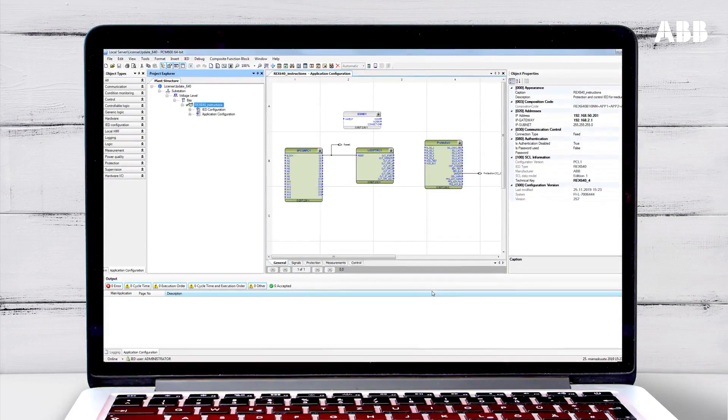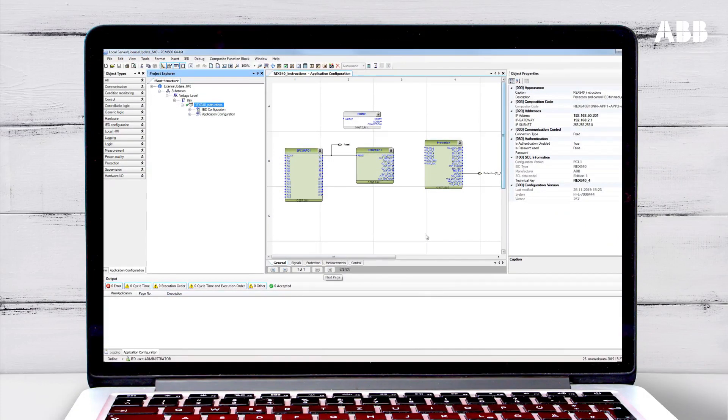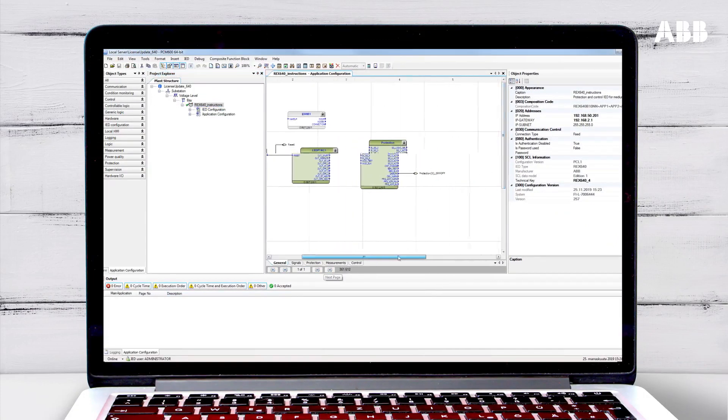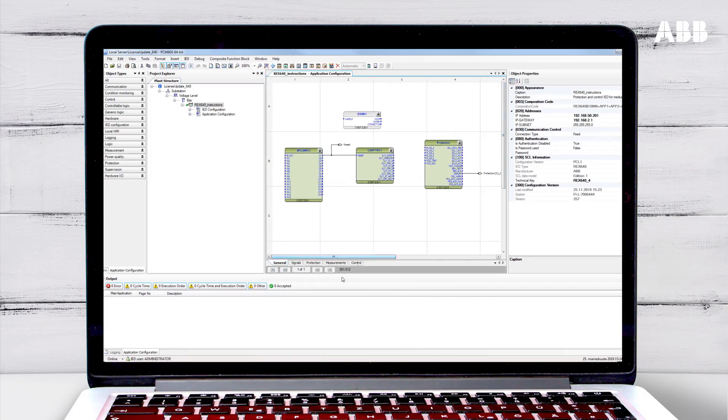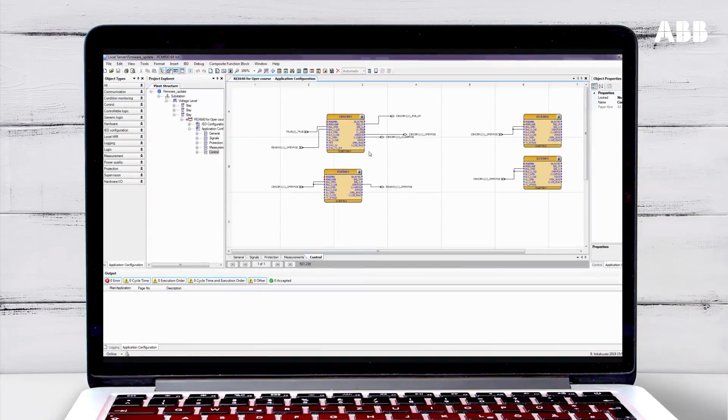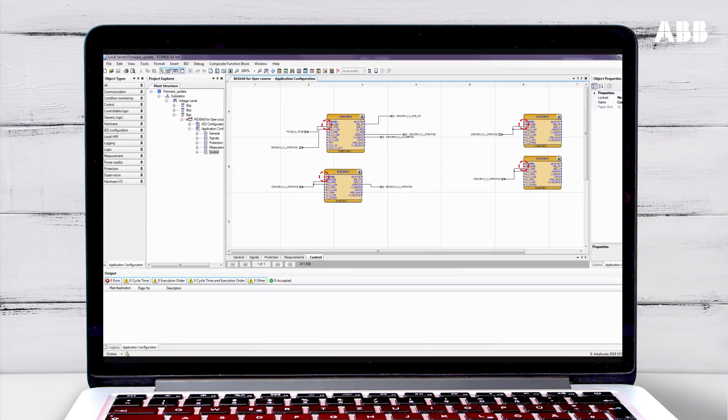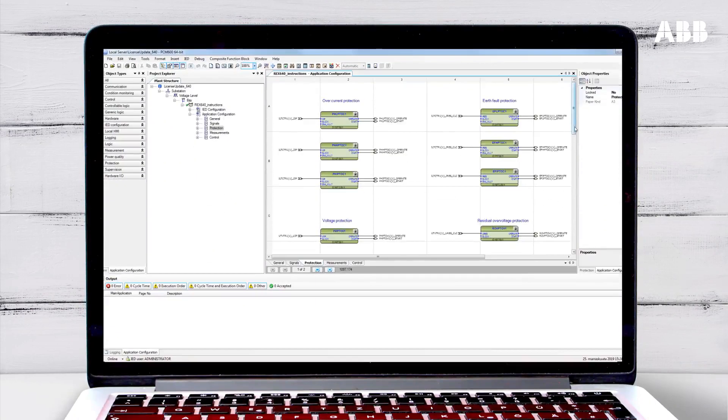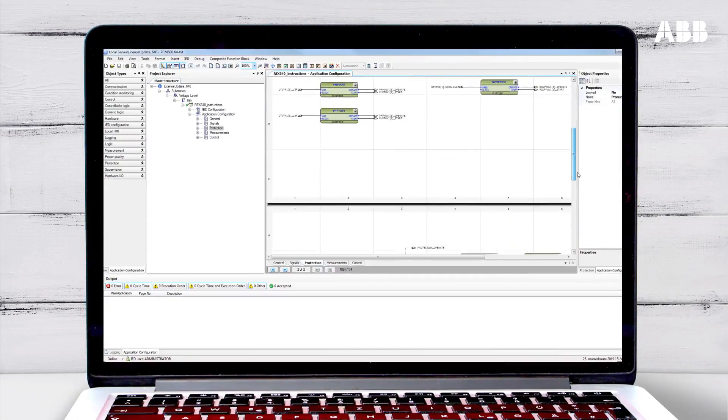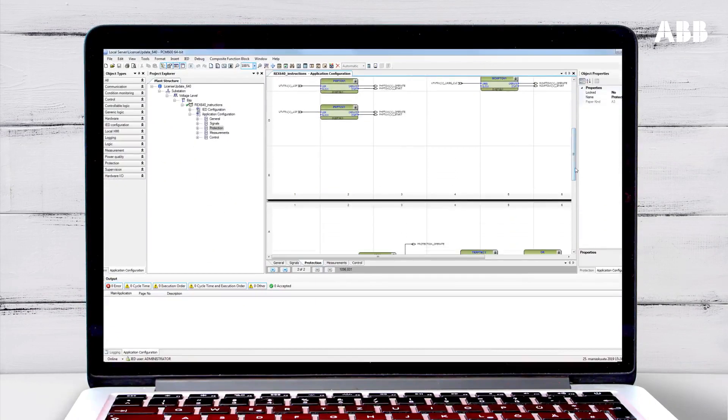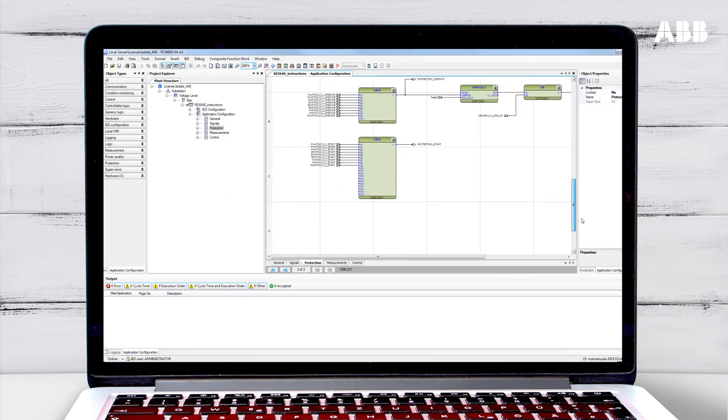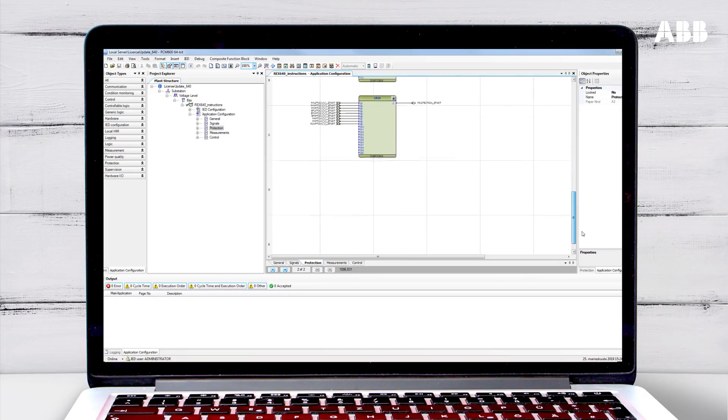Here you can see the application configuration, which will show any changes that have been made to the relay configuration. You need to check the report to see if there are any problems. For example, if there are any compulsory inputs or functions missing. If anything is missing, or if new functions or inputs and outputs need to be added, then you will perform normal relay engineering to add these.